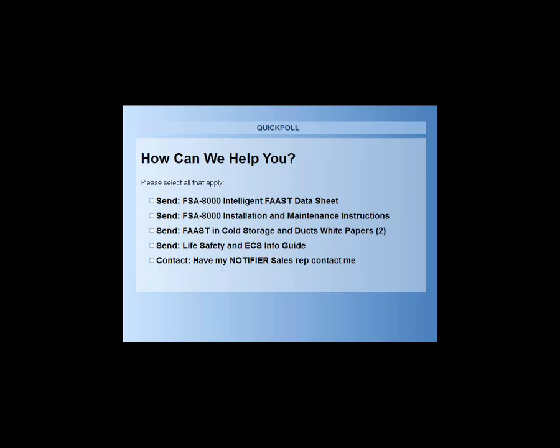Couple questions on testing. How do you test the system? How is the system tested for annual fire alarm inspections? Who can address that one? Yeah, I can take that one. When you design the system using PipeIQ, you'll get calculations for transport time from each sampling hole. The way to do an initial commissioning test of a FAAST unit is to go to the farthest sample point in terms of transport time, which will be indicated on your pipe layout report from PipeIQ. You introduce canned smoke to that sample port and start a timer.